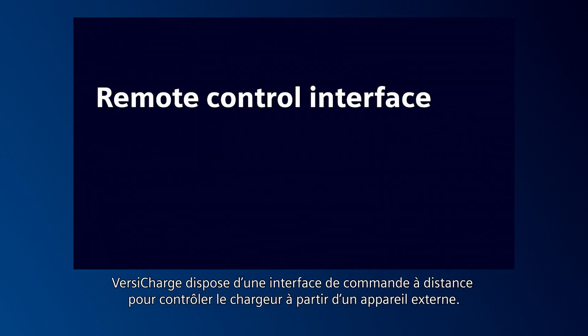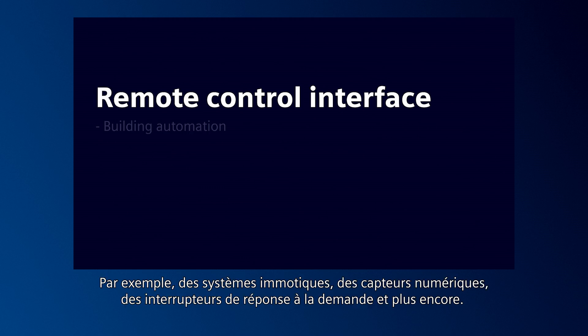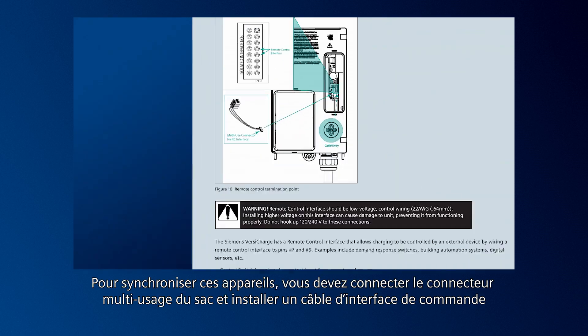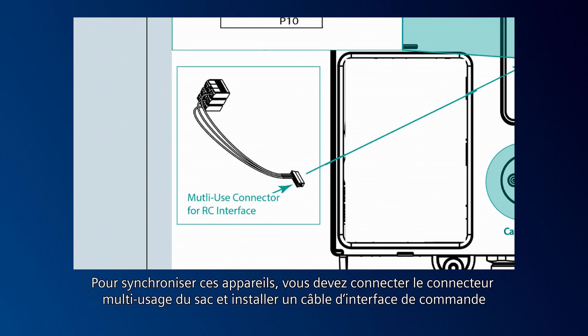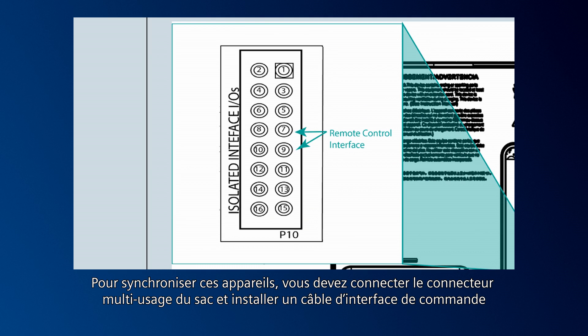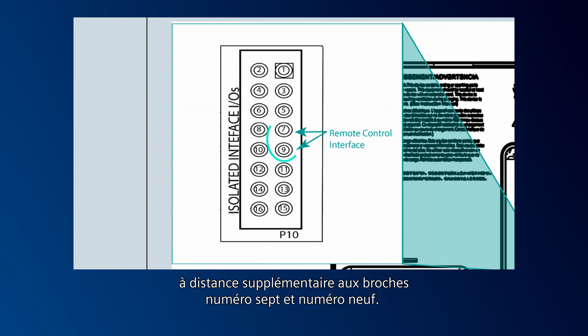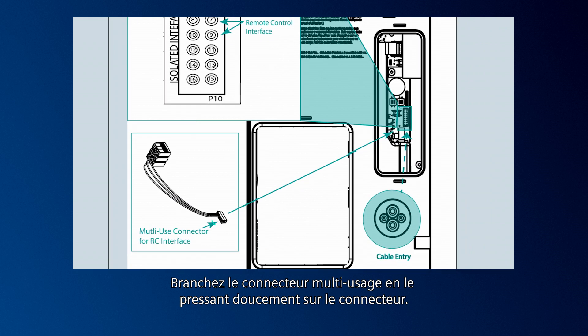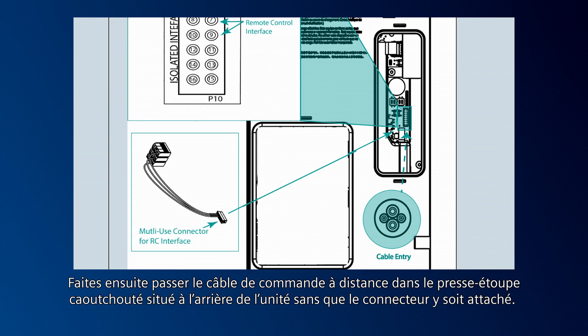VersiCharge has a remote control interface to control the charger from an external device. This could be building automation systems, digital sensors, demand response switches, and more. To sync to these devices, you must connect the multi-use connector from the bag and wire an additional remote control interface cable to pins number 7 and number 9. Connect to the multi-use connector by gently pressing it onto the connector. Then press the remote control cable through the rubberized gland at the back of the unit without the connector attached.